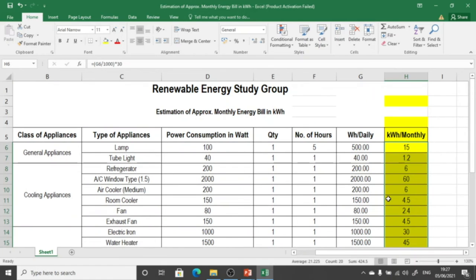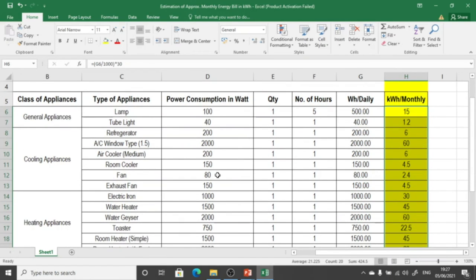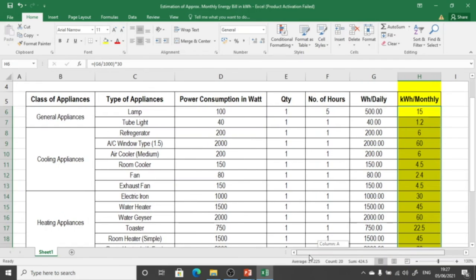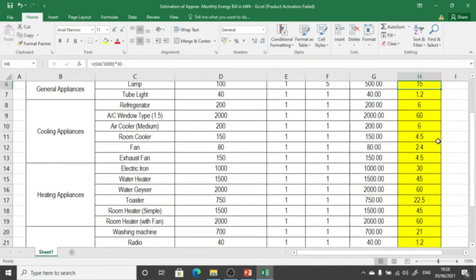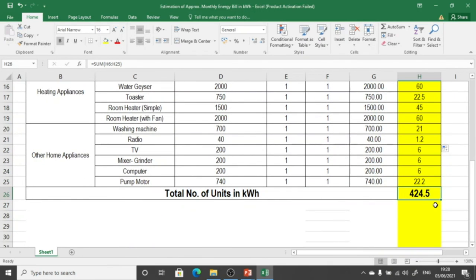Whenever we want to generate an electricity bill or make an energy audit for solar home system design, we check how much equipment is available in the corresponding residential sector and include only that equipment in the calculations. We ask the consumer how many hours each equipment runs as per their requirement, enter the quantities from the audit, and from that we can approximately estimate how much kilowatt-hour the consumer will require at the end of the month.